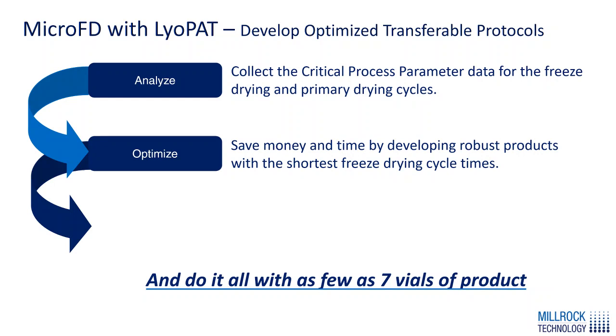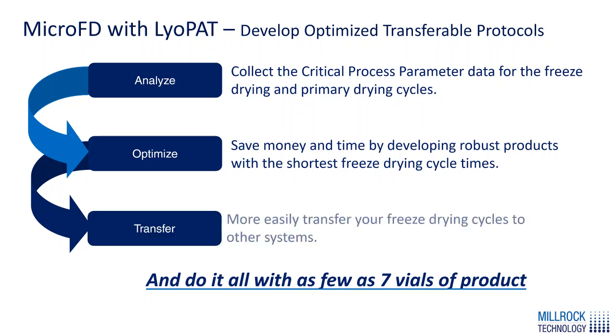Once you've done that, you can go into optimizing the cycle. We give you the tools necessary to change your freezing cycles and your primary drying cycles to develop the shortest freeze-drying time and to develop the critical process parameters associated with those that you can use for transfer. Once you've developed all these critical process parameters and optimized your cycle, you can then transfer the cycle to larger systems. You can do all this with anywhere from 3 to 37 vials.